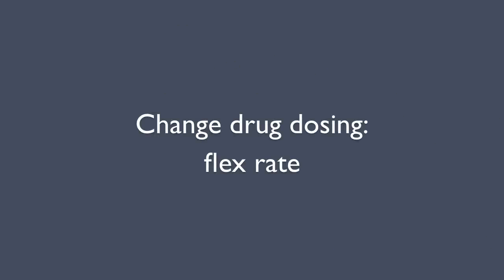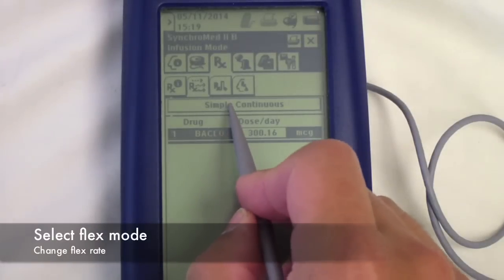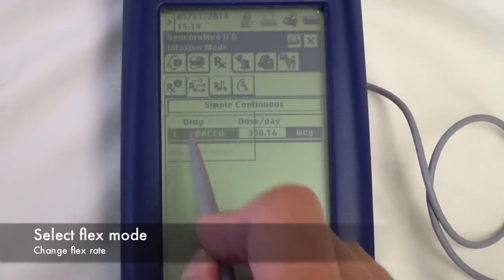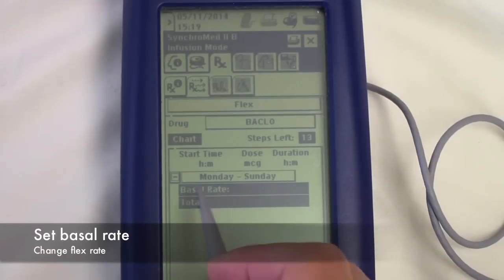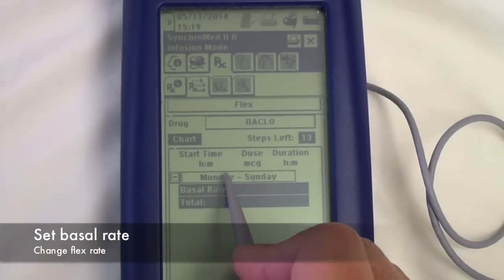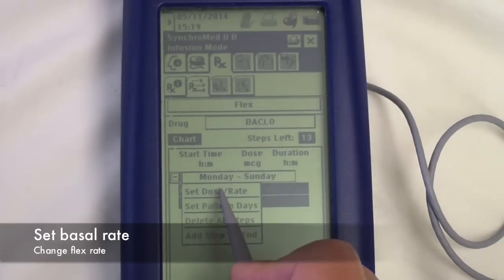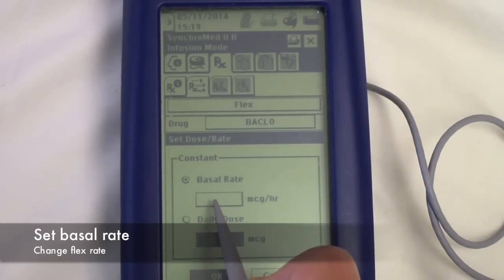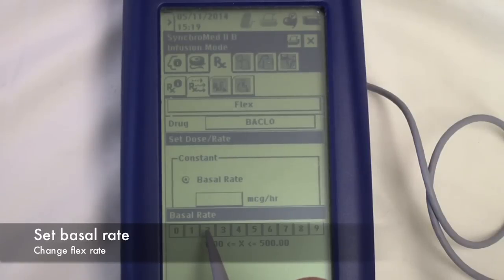Flex mode allows you to set a constant basal rate and add boluses at specified times each day. In this example, we'll set the basal rate at 20 micrograms per hour, but you can also set the basal rate by selecting a total daily dose.